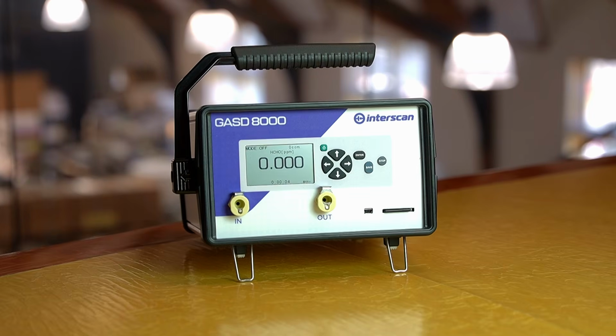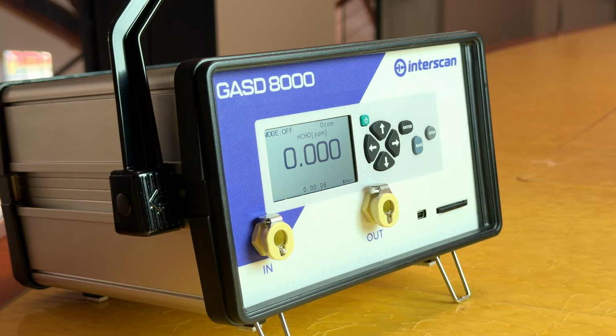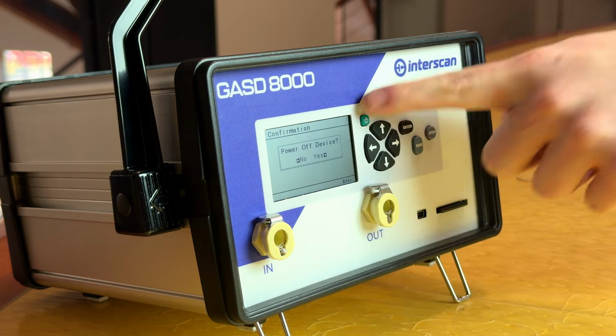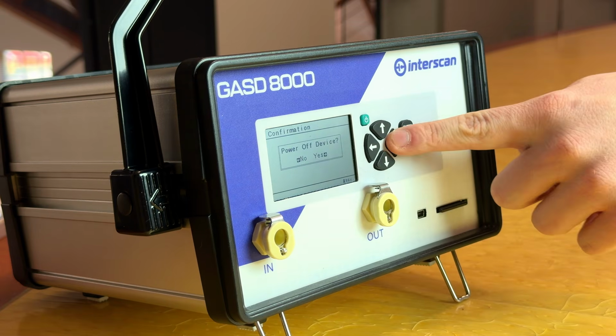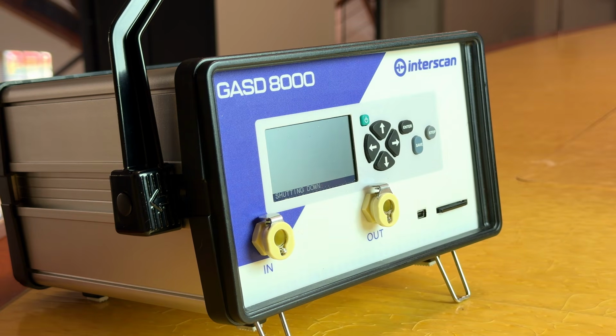To power down the analyzer, return to the main menu by pressing the stop button again. Press the power button and confirm shutdown using the right arrow. The instrument will safely turn off.